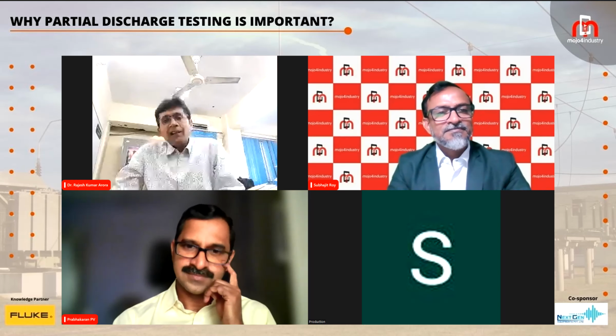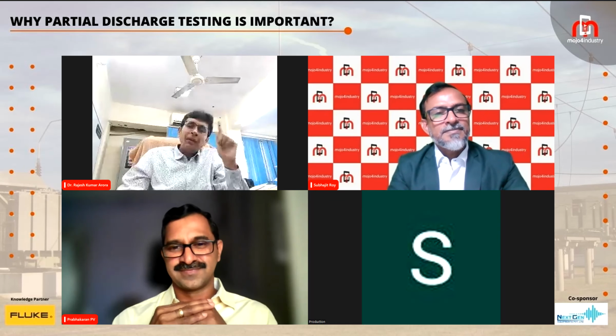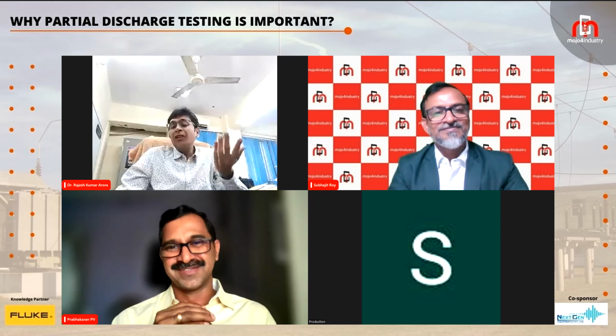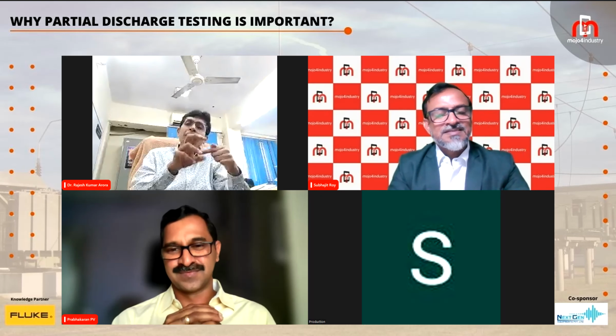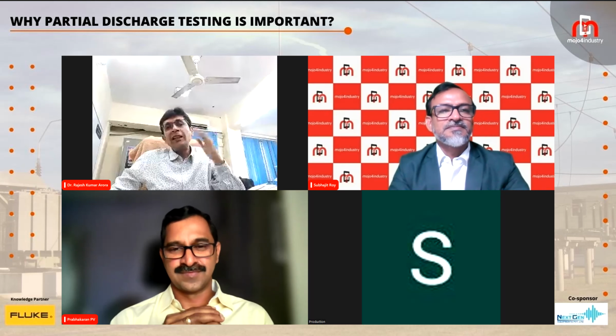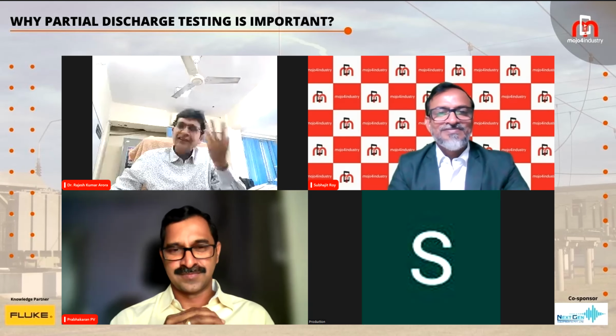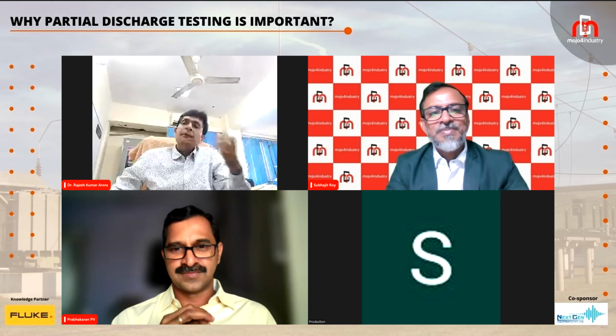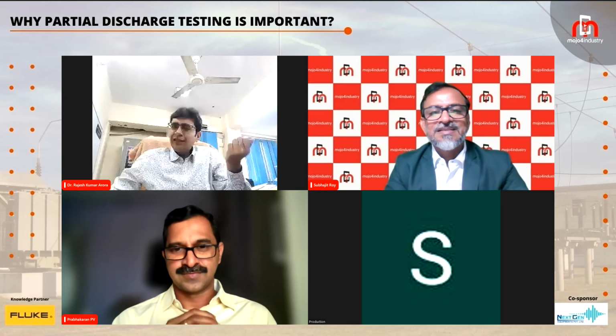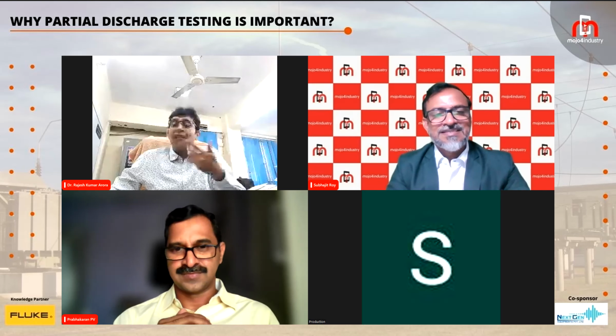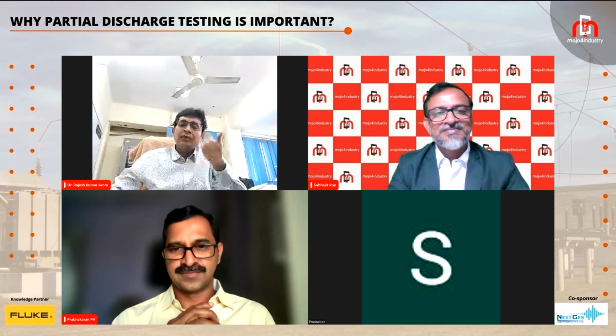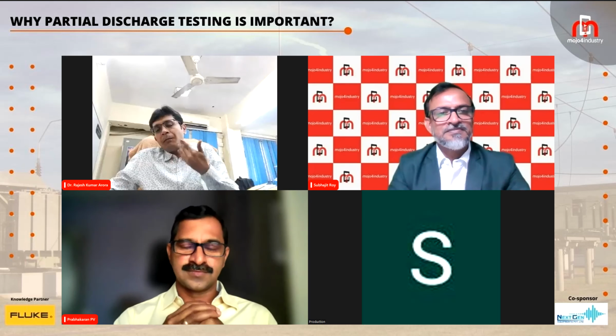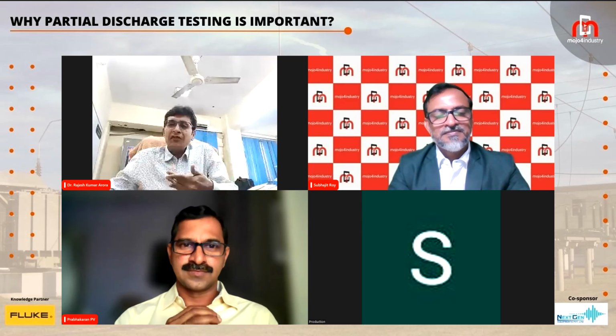As a design engineer, I have already explained the issues. The very first issue is the availability of the type test. When you procure any new technology, you look at the type test governing the equipment. In case that is not available, or the manufacturers are not ready to share it, it becomes difficult to take a call. Even if you decide to procure it, lack of training, lack of expertise, lack of method to analyze the pattern means you are always dependent on the OEM, dependent on the decisions given by that PD manufacturer on what to do next, because you don't have that experience yourself.